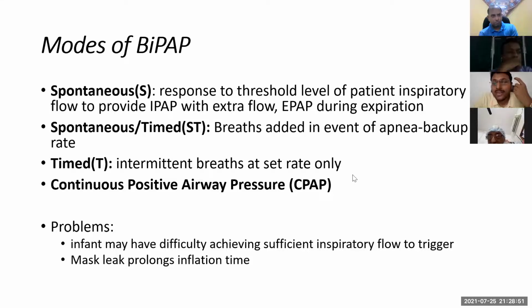So this is very useful. The time mode is very useful for patients who may have something like obstructive sleep apnea. They go into apnea intermittently, and at that time this helps as a backup. So sometimes patients stop breathing, and the machine will give a breath and maintain the ventilation and oxygenation. So both benefits are combined in spontaneous time mode. That is called ST mode. In ST mode, it will let the patient breathe on their own. Suppose a patient is breathing at 40 per minute, it will actually give support for 40 breaths. But suddenly, if the patient stops breathing, the time mode will kick in and take over and give you whatever the backup rate is, like I showed in the previous video. So usually we use ST mode as the default mode because it has the advantage of both modes.